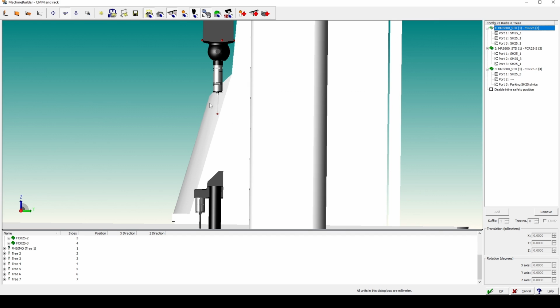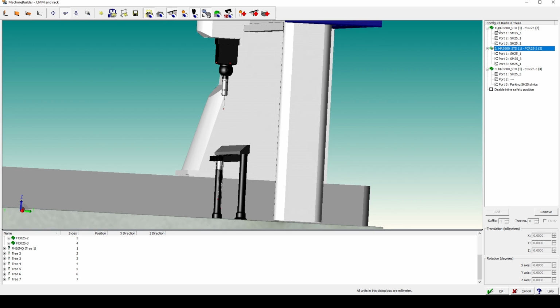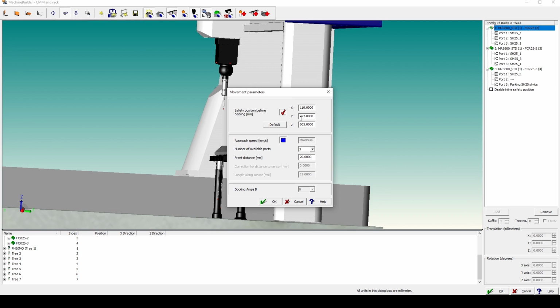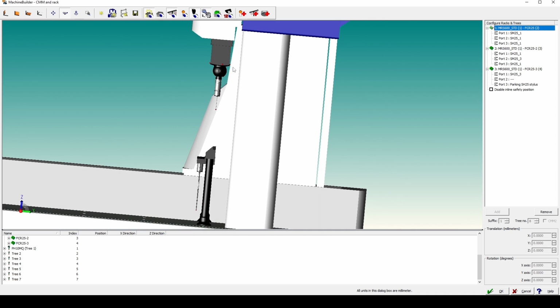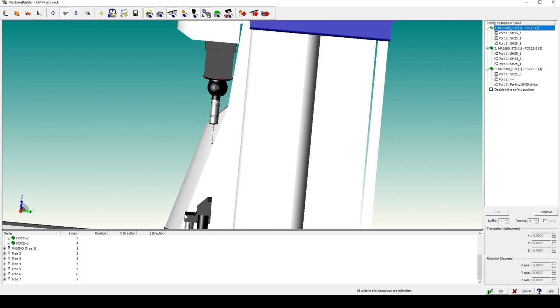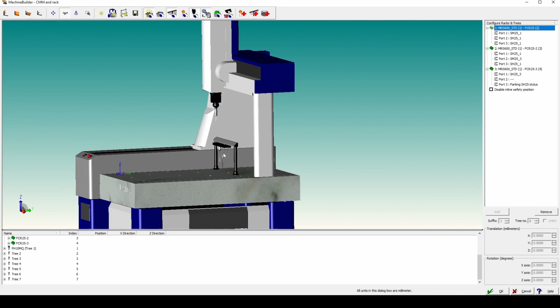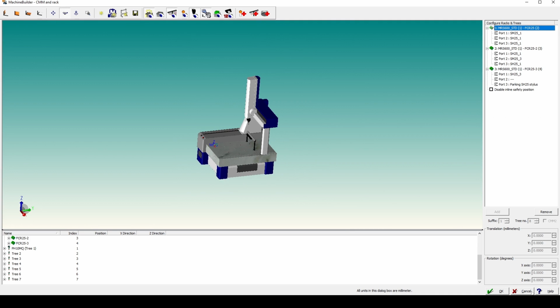So to save a couple of quid for your company, first thing, you just change the Y position from 927, let's say, to 800 or 850, and maybe even move the back position out of your racking system, so you'll not hit the rack or your probe head. And pretty much that's it. That's our CMM. And if you click OK, then it will be saved.